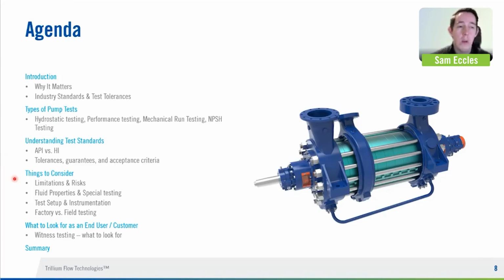We're going to then talk very briefly about how do we handle outliers. So things like, what can testing not tell us? What is testing good at identifying? Is more testing always better? What do you do when it's an oil and gas application and you're pumping propane, ethane, things that bear no resemblance to water? Also, we can talk about high temperature testing, what you do for test setup, what instrumentation we have, and just a quick overview of the differences between factory and field testing.